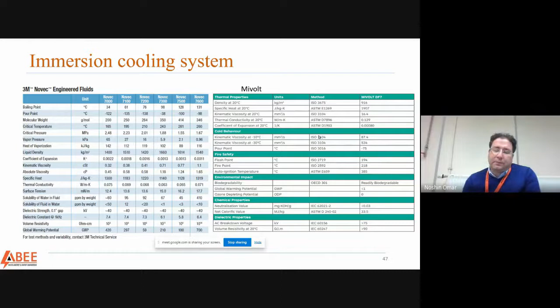Immersion cooling is interesting, but it contributes to the weight requirement. The immersion cooling challenge is that it's 3 to 4 times heavier compared to classical cooling plates, and it's also more expensive because it's not widely used in mass production.